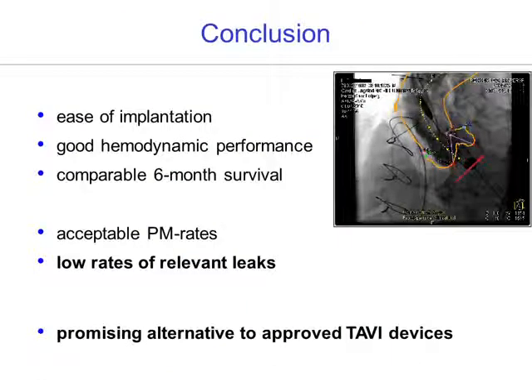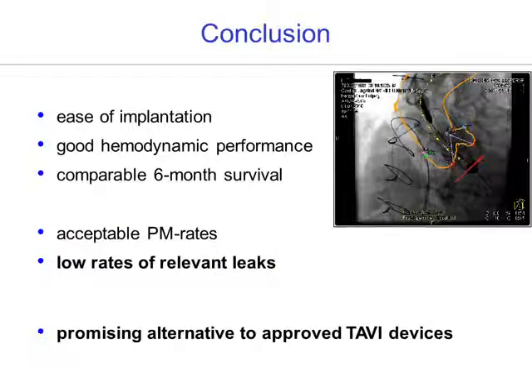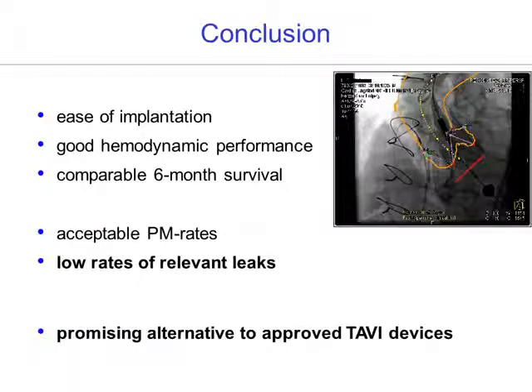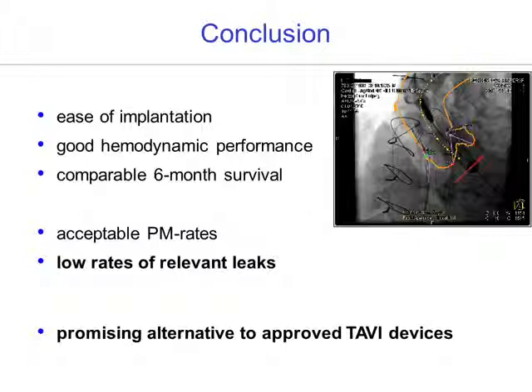In conclusion, the Symetis Acurate device provides a new alternative that is relatively easy to implant. The valve has demonstrated good hemodynamic performance, and the observed six-month survival data compare well with outcomes from other competitor valves. We saw acceptable pacemaker rates, and the particularly low rate of relevant paravalvular leaks is very promising. This new device represents a viable alternative to currently approved TAVI devices.